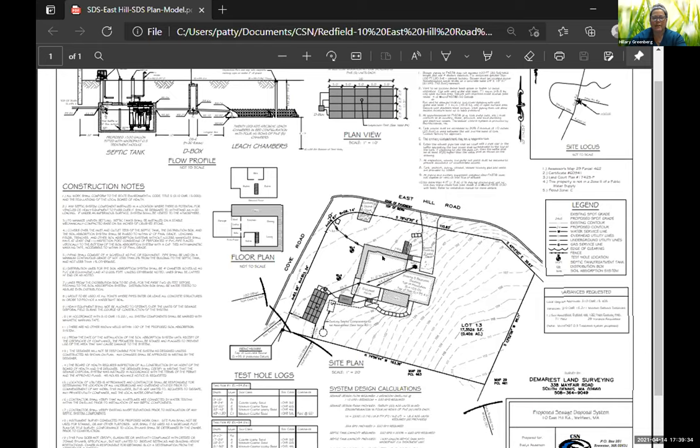3/18/21. And grant the one variance requested in the letter of March 8th, for the upgrade of a septic system to serve a 3-bedroom structure, a grandfathered non-conforming dwelling, using the Microfast 0.5 denitrification technology under the general category. Design flow to be limited to 330 gallons per day to serve 3 bedrooms. No increase in habitable area or conversion of use without Board of Health review, well water testing, deed recording, I/A monitoring, and a clean out to be placed on the building sewer line.